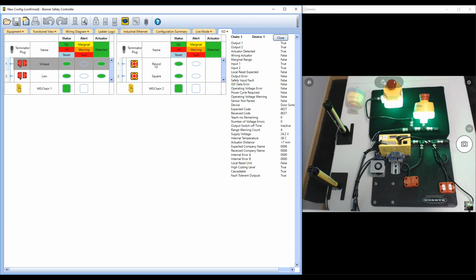They're also asking how many can I have in series off one controller. For each chain, if I've got chain 1, I can have up to 32 ISD devices on one chain. The second chain can also have 32 devices, so a total of 64 into the SE10, and you'll have 6 terminals left over for other stuff.